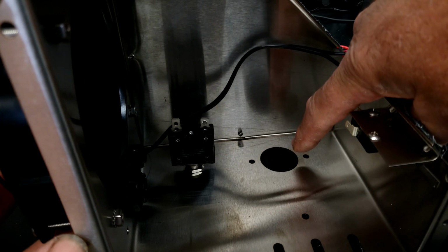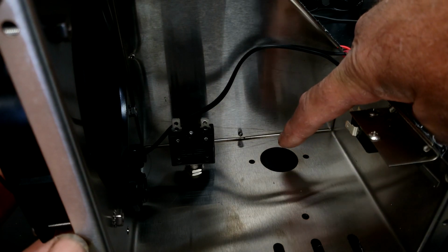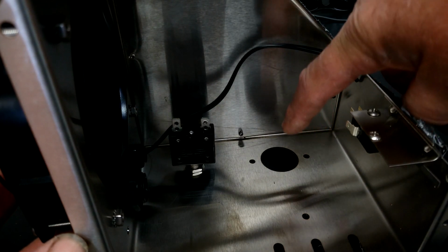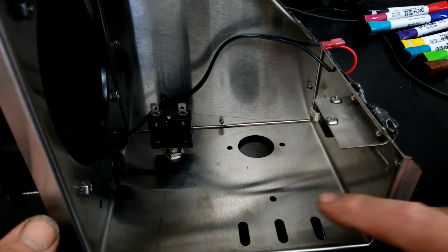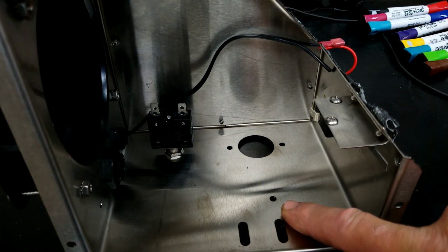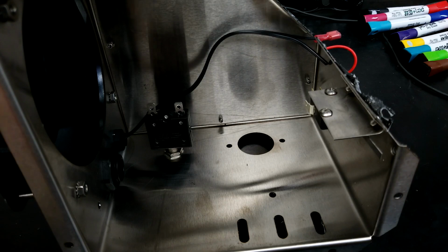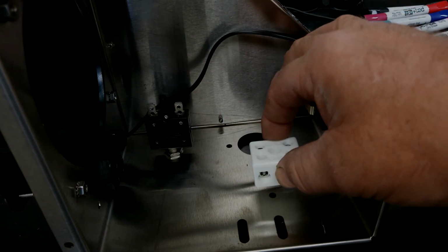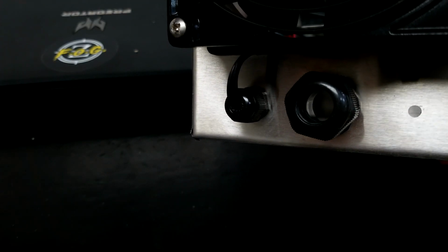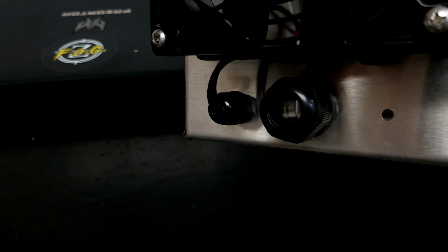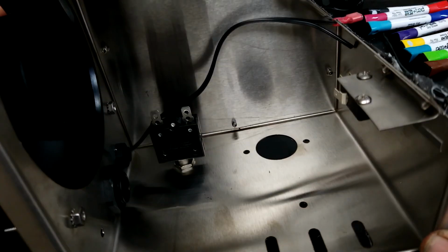And physical location over here for your SSR. Your cooling fins are going to be sitting facing down, and this one little hole right here is for your terminal block. You've got your power cords, your main power that comes in that big bushing, and then the little hole is for a small bushing to run the power out to the cooling fan. Okay, so we're done talking about all the physical locations of all this stuff.